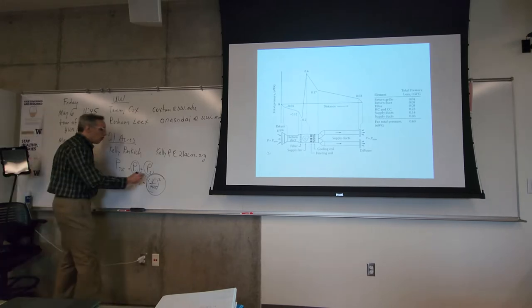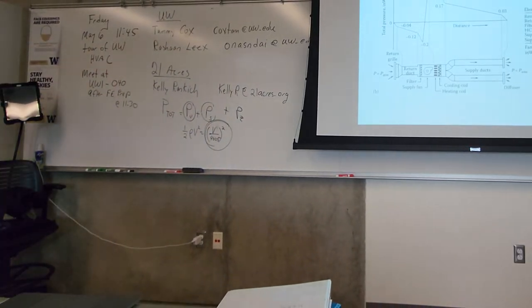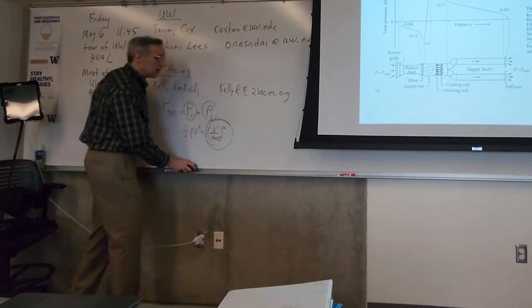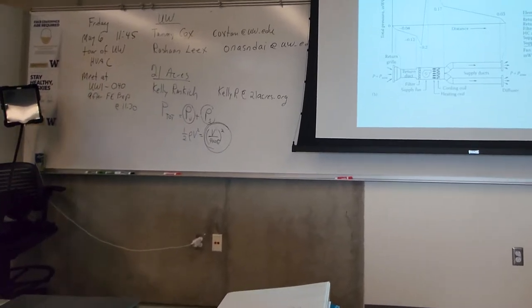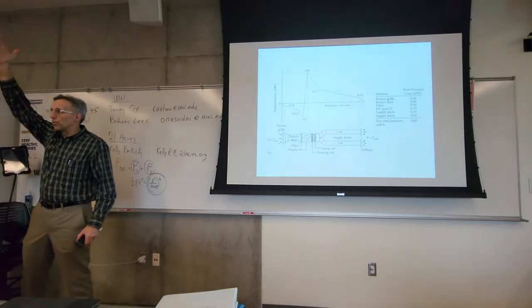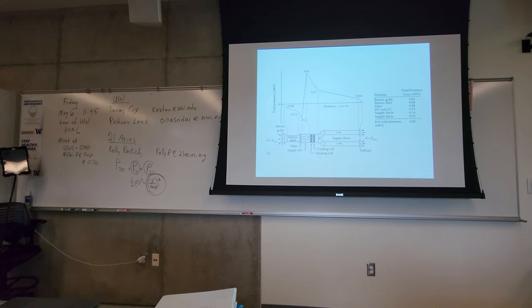And then when we get to pumps and water flow, we have to add the elevation head, which is the energy that you need to push the liquid up a vertical distance. But we don't worry about that with the air. I don't even think we worry about moving air up a really tall building. Actually, these calculations do get really interesting with tall buildings, especially with water. If you've got water moving around a hundred story building, that's a massive amount of elevation head. So if your liquid piping at the lower floors is connected to the liquid piping at the upper floors, your lower floor piping is going to be really thick wall. It's going to have to be reinforced to withstand all of that force of gravity that's pushing down.